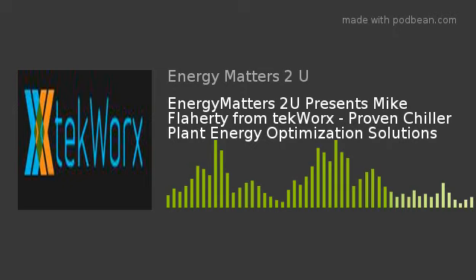Generally speaking, this approach can save somebody around a quarter of a kilowatt per ton-hour, somewhere between 0.2 and 0.4 kilowatts per ton-hour. If you multiply that by the energy you use for cooling, and the cost per unit of energy in a place like New England, where you're paying 14, 15, 16 cents a kilowatt-hour, you can usually be effective down to plants with maybe 400 or 500 tons of installed production.